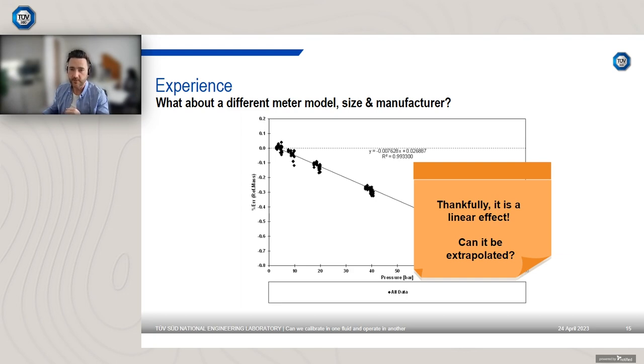So this is the equation. You can see y equals minus 0.007628. So ultimately that's your pressure effect. You can see the intercept there as well. That's ultimately the offset, so the meter's slightly overreading by 0.027%. Minuscule. You could adjust the mass factor by that. But the first term is your pressure effect. That gives you a traceable pressure compensation factor.